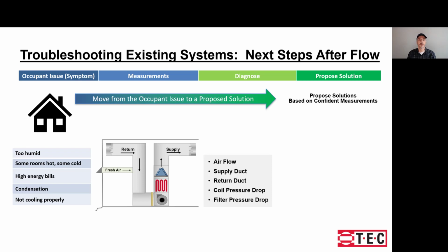Oftentimes, in addition to airflow, on the air side, what we want is to measure a series of air pressures. You know, the supply, the return, and then pressure drops involved across the coil and the filter. That will allow us to look at the external static pressure as well as these individual pressures and airflow. And by having all that information, now we can start to diagnose what is causing the issue and what we should be proposing.